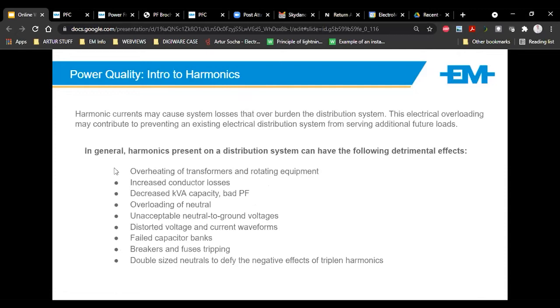So harmonics may cause system losses that burden the system. Typical things that can happen: overheating of transformers, decreased kVA, a bad true PF. The big one is the overloading of a neutral. This is typically when you've got single phase switch mode supplies. A high current harmonic results in a high distorted voltage harmonic, typically. If you had a normal PFC system that's not protected, it typically causes capacitor bank failures, because a capacitor which is not protected will overload and cause breakers and fuses to trip. So in general, depending on how bad the percentage is, it can create other negative effects on your power network.